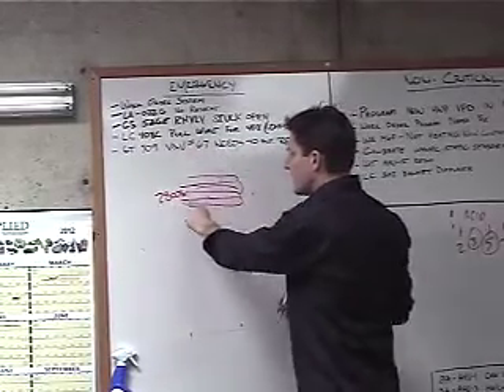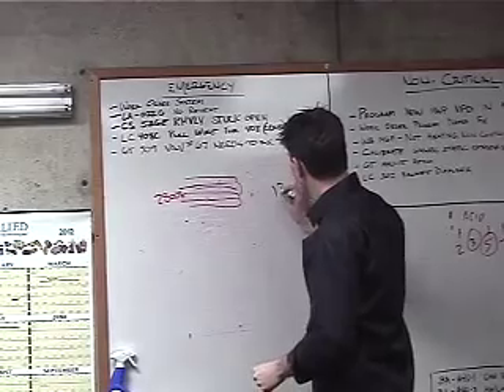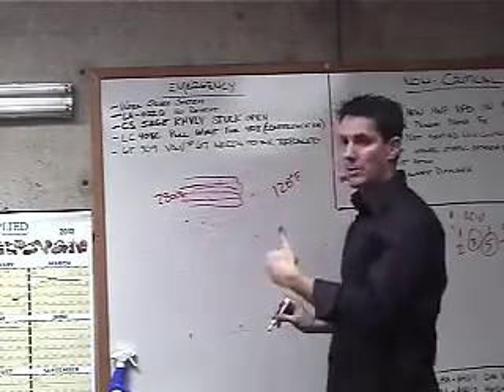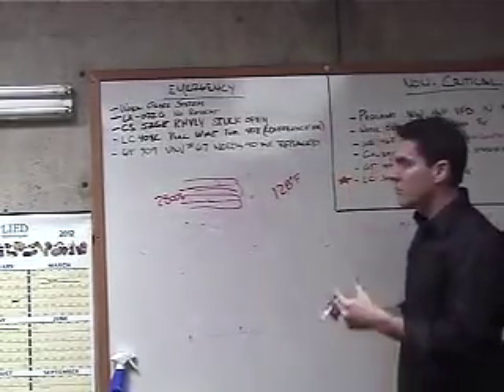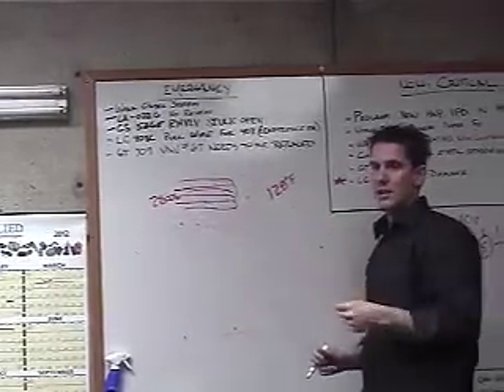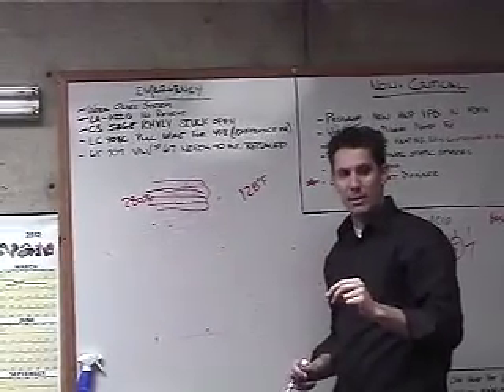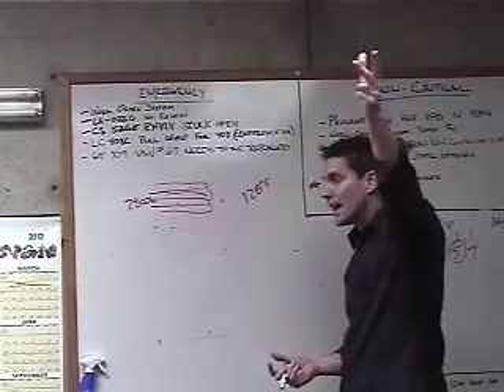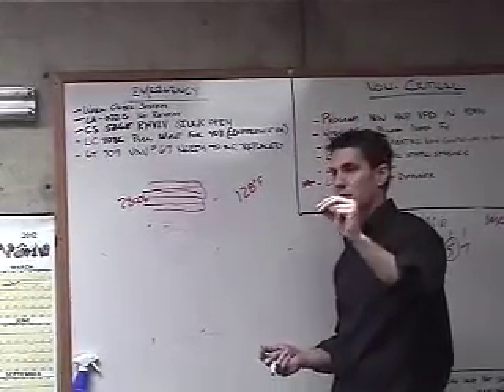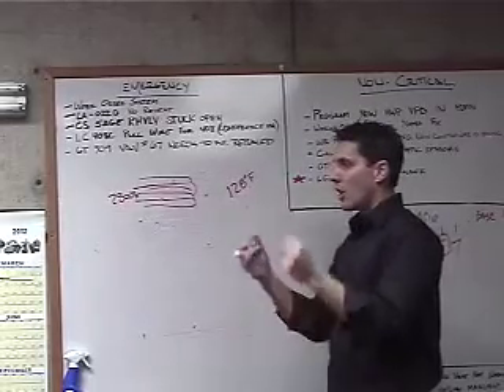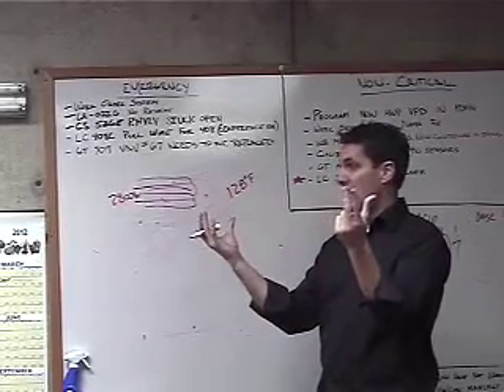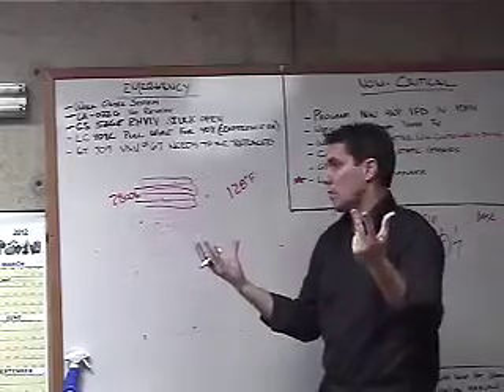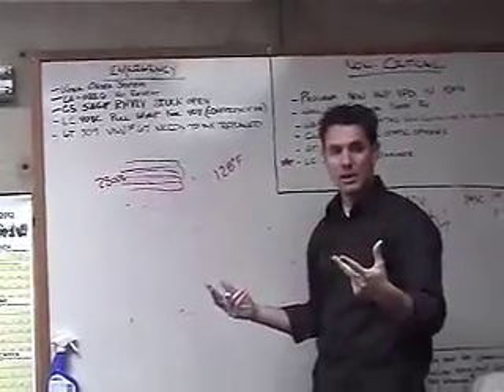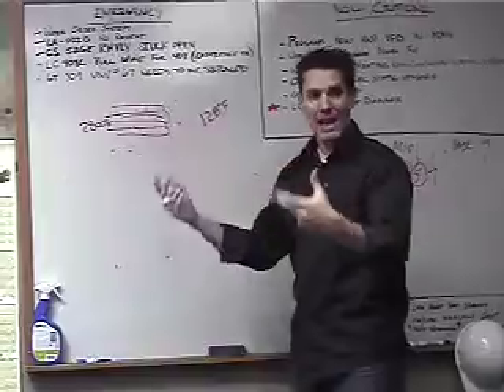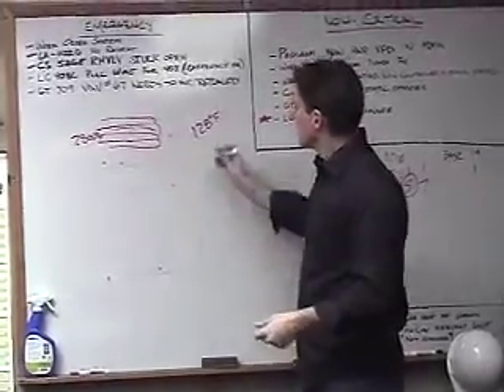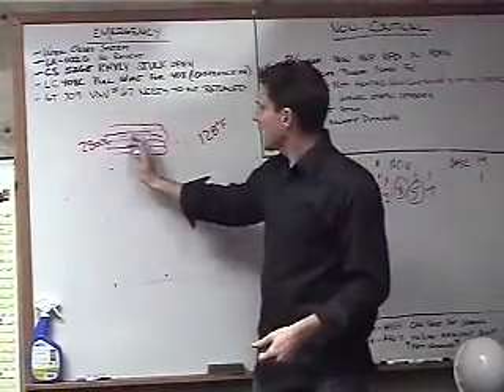You will not start to condense that water vapor in here until 128 degrees. And I wish we had time so I could explain that to you. But once my flue products reach 128 degrees Fahrenheit, that is the dew point temperature of all of my water vapor. So just like the clouds outside, once you reach the dew point temperature of your air and water mixture, then all of that gas, the steam, will rain out. And as it does, it gives up all of that heat energy. So we're giving that heat energy up so that it can get back into the metal and back into our water. But it doesn't happen until 128 degrees. That's not occurring up here.